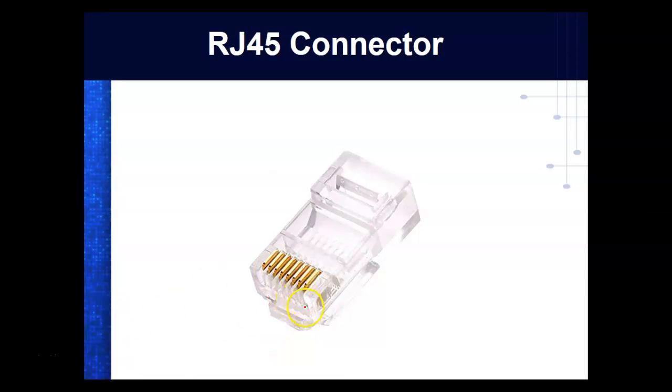So what we can do is we can actually see the wires, we can see the tips, and we strip them. When we strip the wires, they're going to be circular. And then the metal tab, the actual conductor, is going to be inside the insulator. When we push it in there correctly, and this is going to be solid strand copper, we should be able to see these little copper dots sticking out the end. And when we insert it, we have to get it in far enough so the jacket is under this crimp right here. So I'll show y'all how to do that.